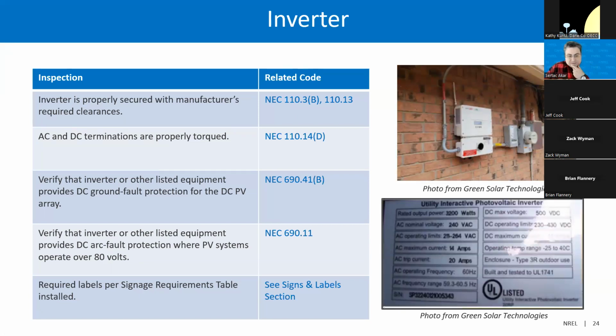So after racking, the next thing to check is the inverter. First, the inspector should verify that the inverter is properly secured with the manufacturer's required clearances, and check that AC and DC terminations are properly torqued. Second, the inspector should verify that the inverter provides DC ground fault protection and DC arc fault protection where PV systems operate over 80 volts. And last, the labels should be per the signage requirement tables as installed.